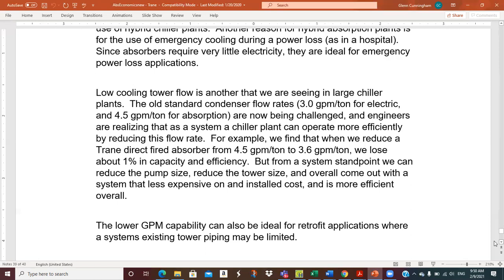If you create a cooling tower from the chiller plant in the HAP program, and it's for an absorption chiller, it will default to 4.5 GPM per ton. You can set it to whatever you want within, I'm sure, some range. But here they're showing the Trane direct-fired absorber down to 3.6 GPM per ton, which is 9/10 of a gallon per ton. That's quite a bit of water on a big machine.